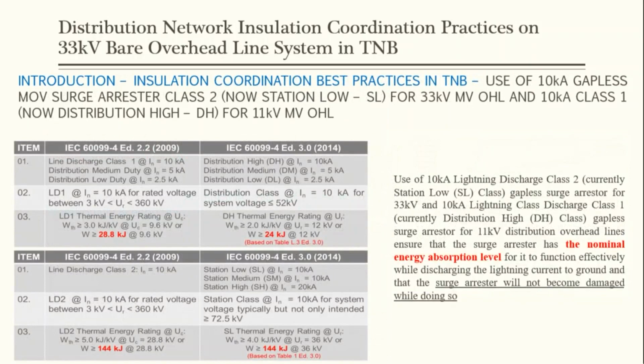Okay. Then next, the use of 10 kA gapless MOV surge arrestor class 2, now known as station low or SL, for 33 kV medium voltage overhead line, and class 1, now known as distribution high, for 11 kV medium voltage overhead line. Why? Because these two will ensure that the arrestor has the nominal energy absorption level to function effectively while discharging the lightning current to ground, and that the surge arrestor will not become damaged while doing so, especially when you have multiple lightning strikes at the same spot.